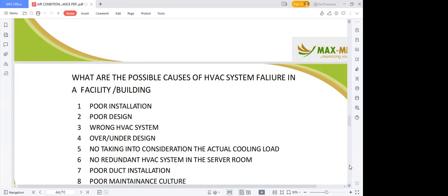Poor HVAC system choice. You use the wrong HVAC system for the building. Just imagine somebody says they should put a split unit in a stadium. How many split units are you going to put in a stadium to cool the entire stadium? That does not make sense. Then some issues could be oversizing. When you oversize your AC design, it has a direct impact on your energy consumption. When you undersize the design, it has a direct impact on the comfort of the building. Please take note.